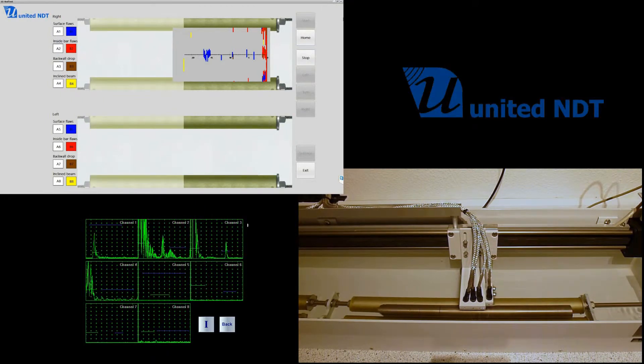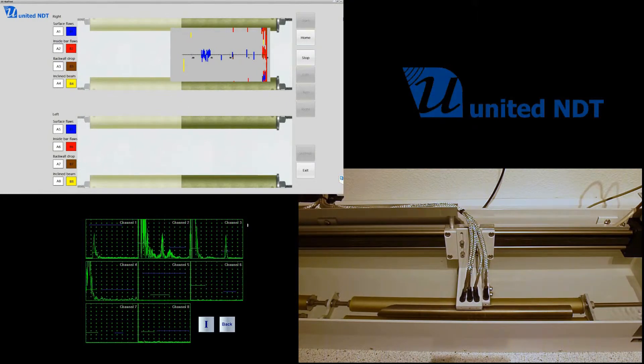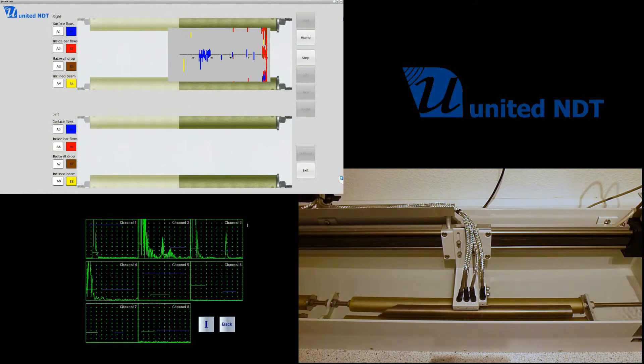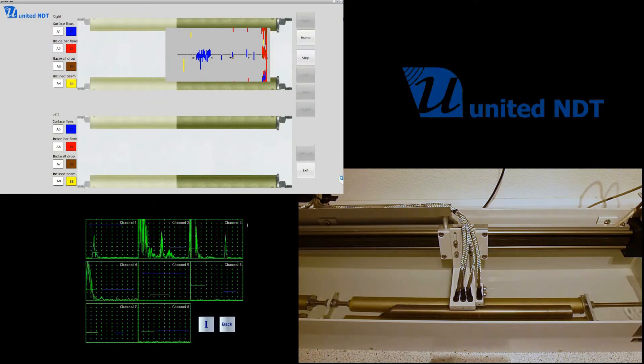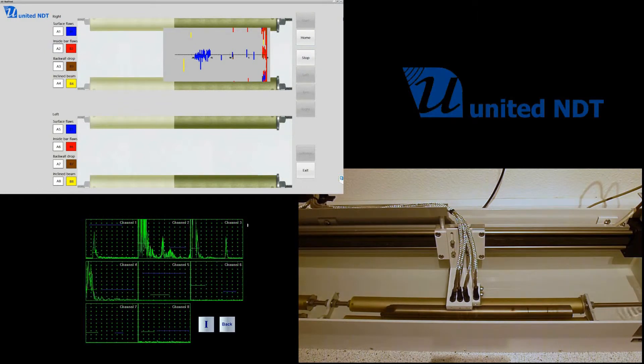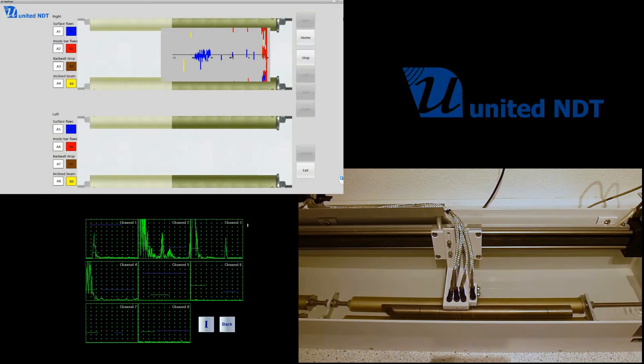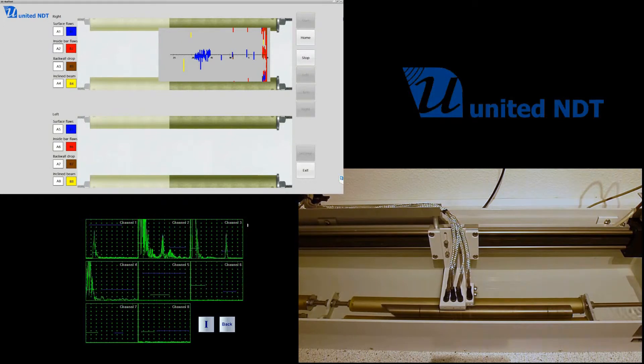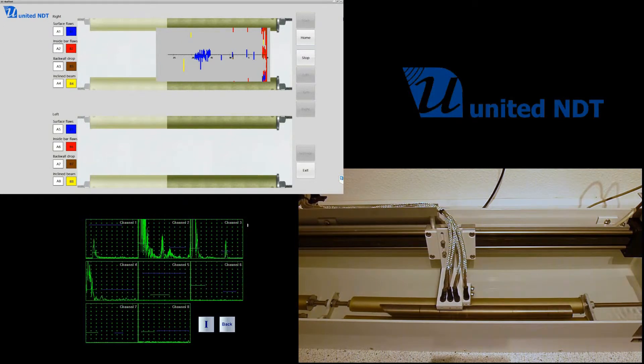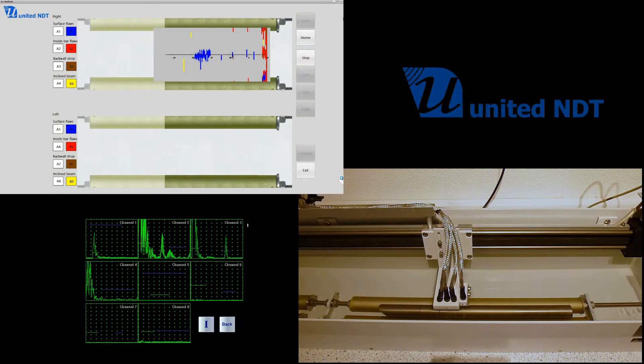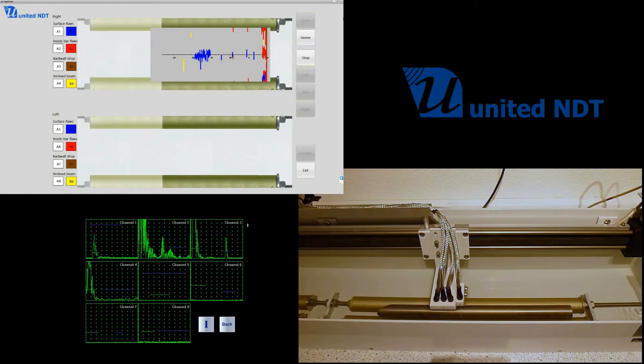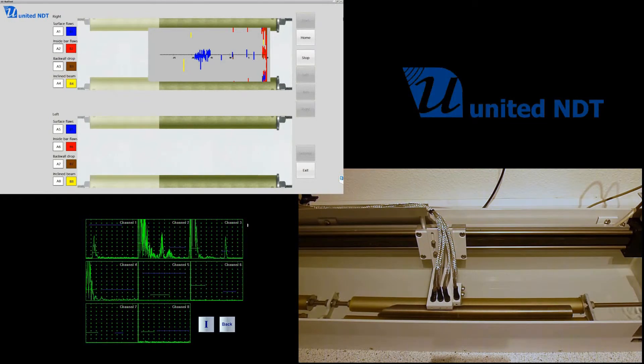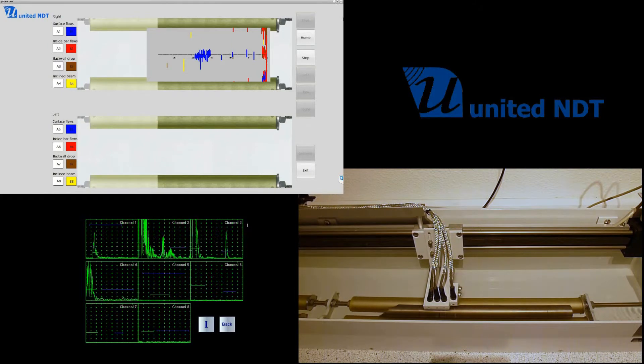And we see the results on the top left in real time. For example, the red spots or red areas—the red indications are for inside flaws, the blue ones for surface flaws, the yellow ones for inclined flaws. All flaws are color-coded on this image.